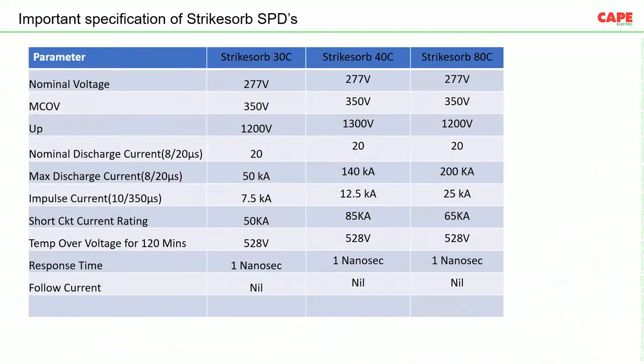These are some important parameters of the busbar mounted SPDs. For nominal voltage, I have taken a certain series of voltage which is normally used in India: 277 volt, which has an MCOV of 350 volt for all three models, Strikesorb 30, 40 and 80C. Nominal discharge current is the same for all three models. Again, it is a test method; they test it with 20 kiloamperes only. Maximum discharge current for Strikesorb 30 is 50 kiloampere, Strikesorb 40 is 140 kiloampere, and Strikesorb 80 is 200 kiloamperes.